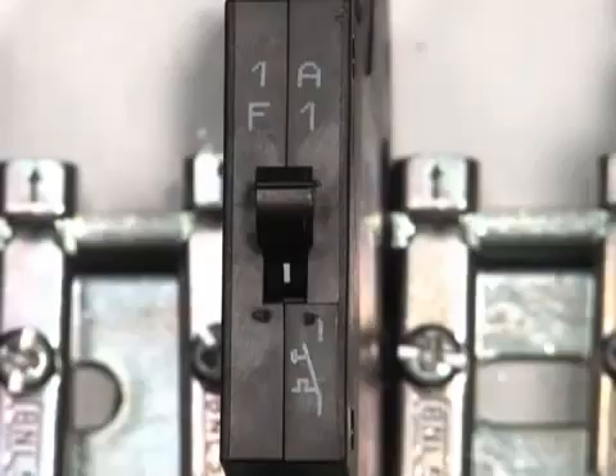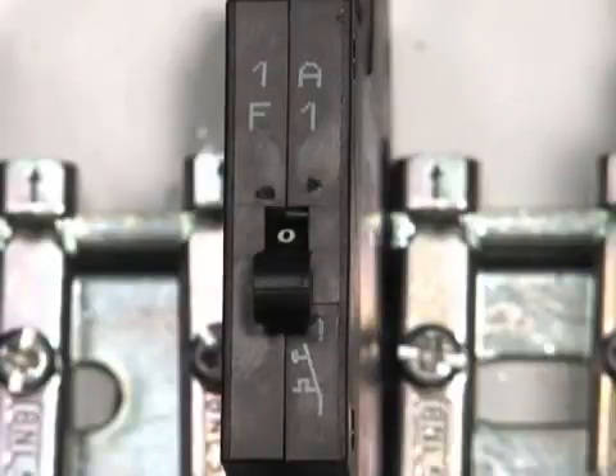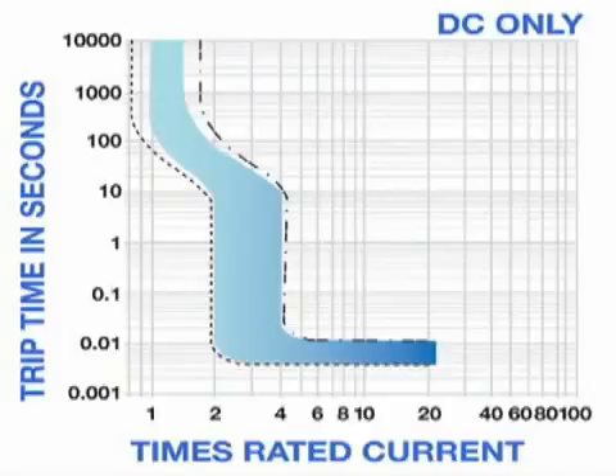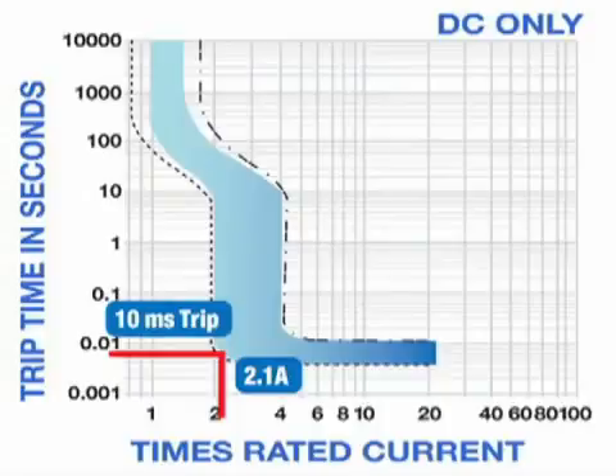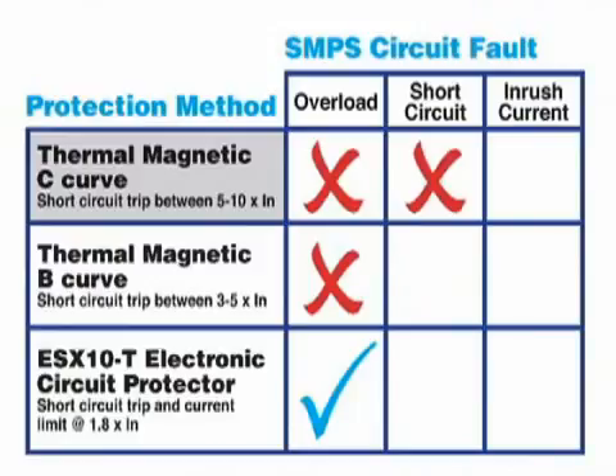Notice the short circuit being interrupted by the magnetic response to the breaker. When the short circuit current reaches 2.1 amps, the fast-acting magnetic response triggers the breaker. The voltage stays at 24 volts DC, and all other loads connected to the power supply are operable. This is the desired operation of a circuit breaker. However, there is a drawback to this approach, as you will see later.